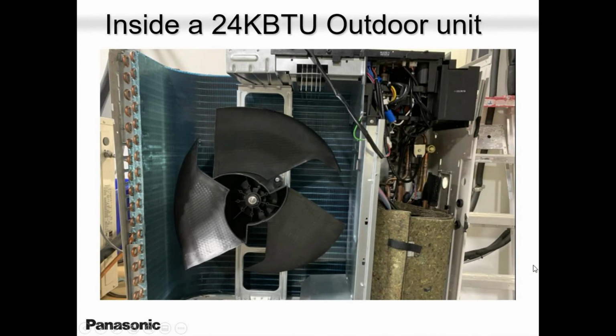This picture is a live picture that I got 2-3 weeks ago from a customer, and he thought that this unit, the base pan heater, wasn't working. But in reality, the problem was low on refrigerant. So always remember, if your unit is equipped with base pan heaters, which most of the units are, and you have this situation, you definitely are low on gas. Why? Because your defrost cycle was not hot enough to melt everything.